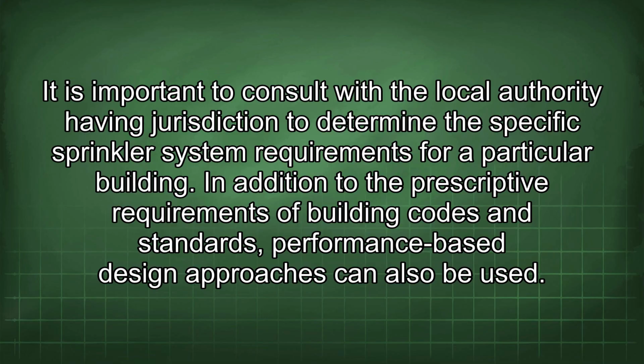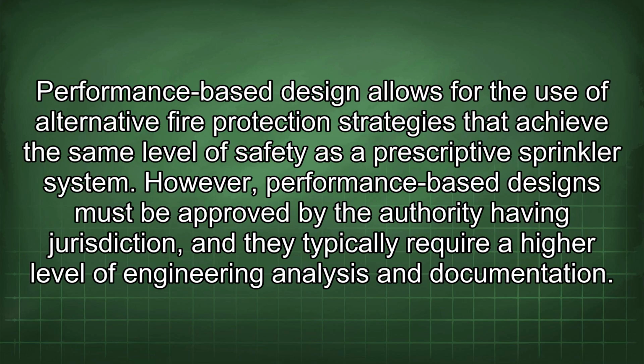In addition to the prescriptive requirements of building codes and standards, performance-based design approaches can also be used. Performance-based design allows for the use of alternative fire protection strategies that achieve the same level of safety as a prescriptive sprinkler system. However, performance-based designs must be approved by the authority having jurisdiction, and they typically require a higher level of engineering analysis and documentation.